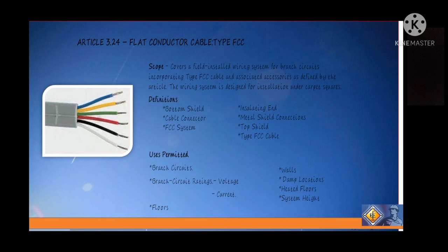So for the scope, it covers a field installed wiring system for branch circuit incorporating type FCC cable and associated accessories as defined by the article. So the wiring system is designed for installation under carpet squares. So the definition of flat conductor cable includes bottom shield, cable connector, FCC system, insulating end, metal shield connections, top shield, and type FCC cable.